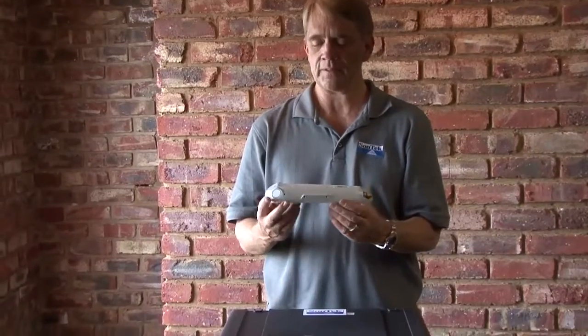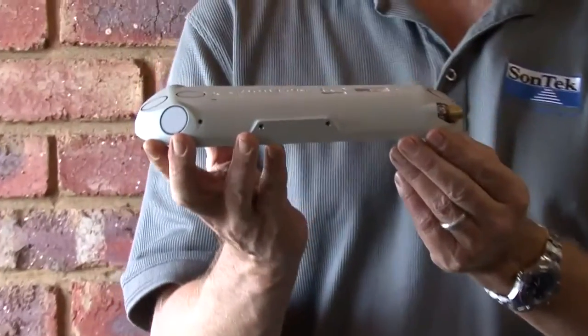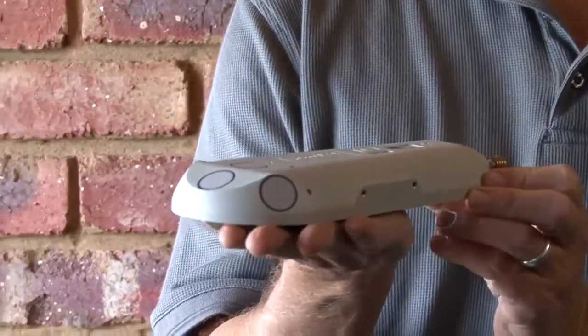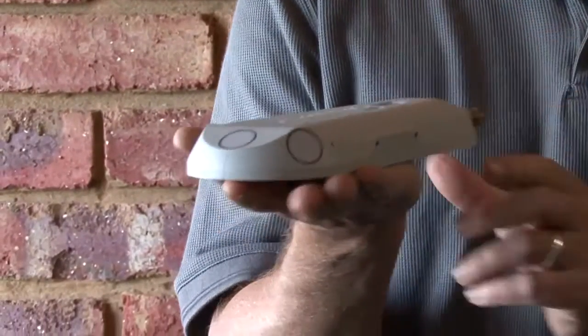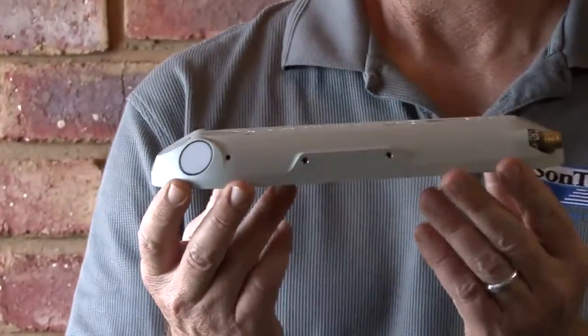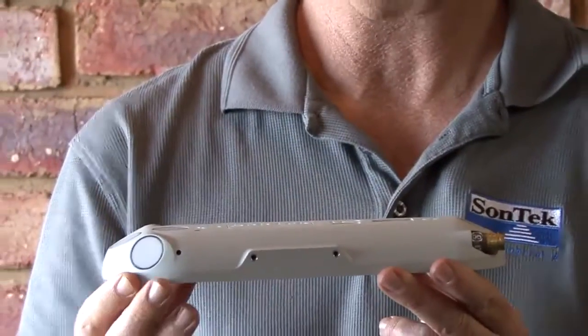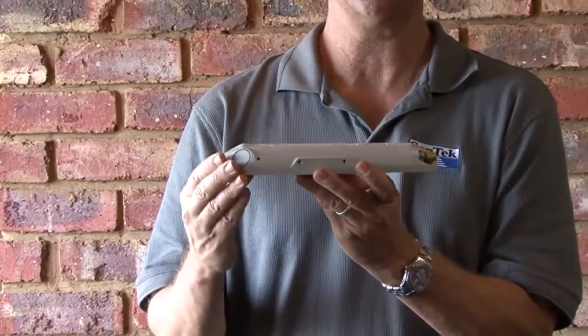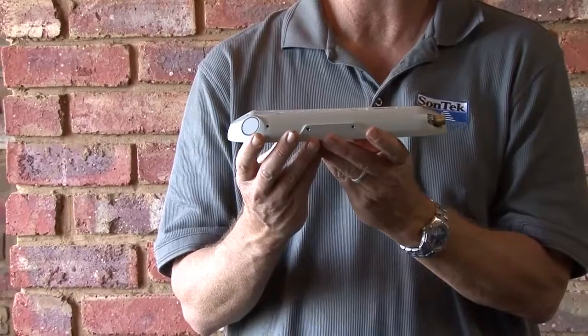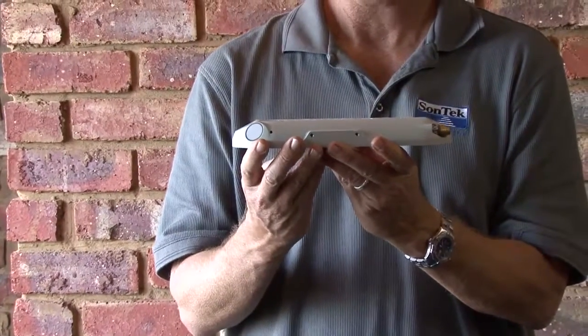So let me talk a little bit about what's inside this instrument. As you can see, it's a very low profile. We've designed it this way to provide minimum drag in the bottom of the canal, which allows you to mount it much lower to the channel bottom. It also disturbs less flow, so it allows you to measure accurately in much shallower water than previous instruments.